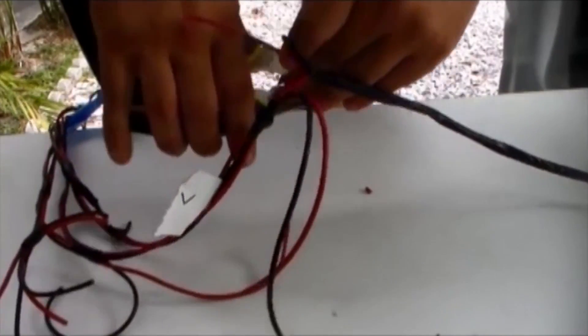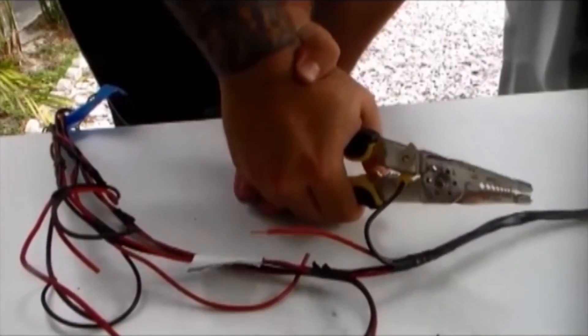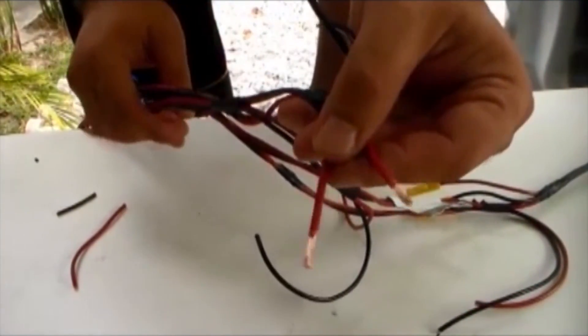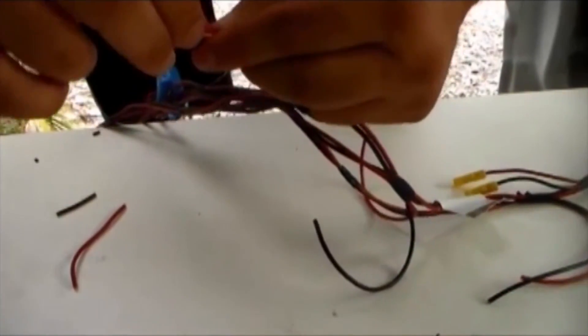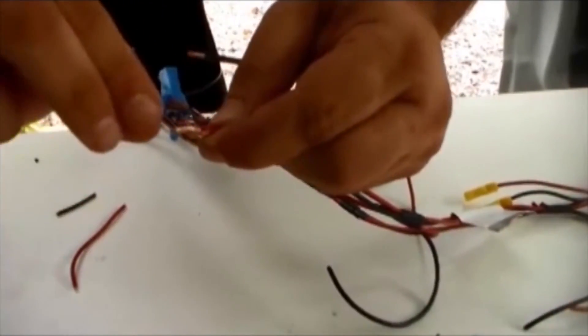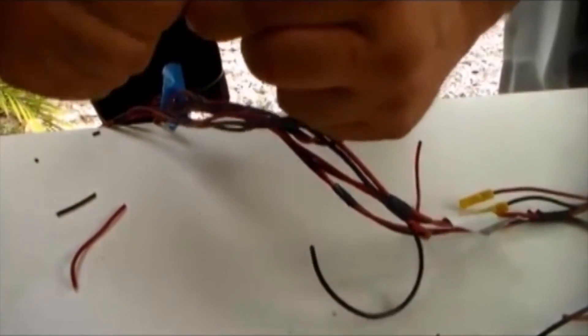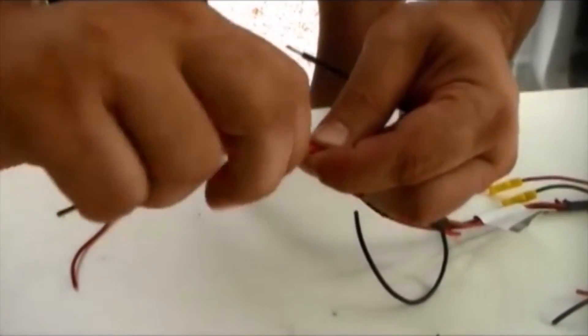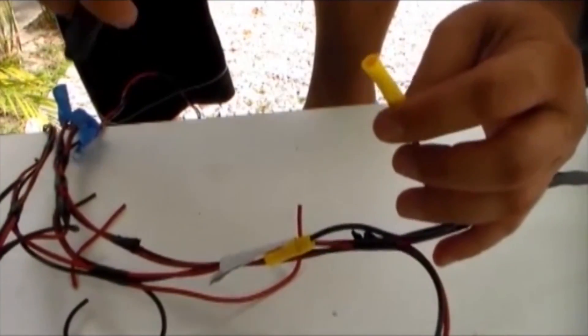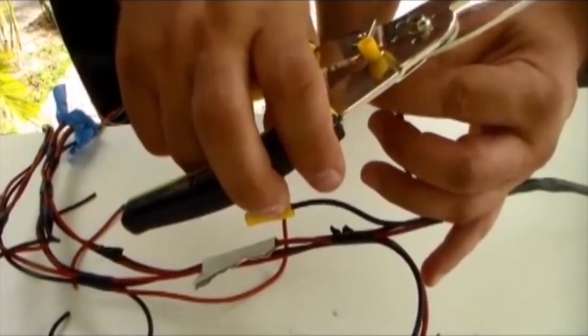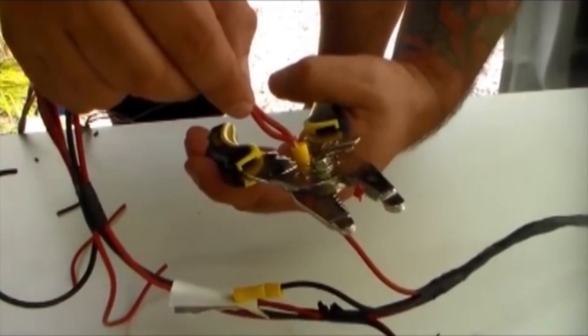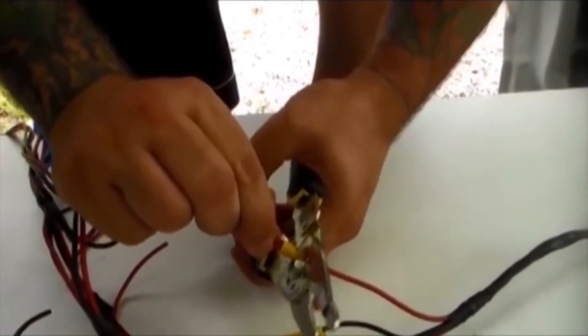Crimp it, make sure it's on there tight. You don't want it coming loose. There's the two wires. I got them stripped back further than I normally would because these two need to get twisted together. Do a very extreme twist with it like that, make sure they really wrap around each other so one doesn't slip loose. Then that will fit in that side. I'll get the crimp ready. Hold it and look down inside to make sure neither wires snag, that it slides in smoothly. All the way in there, then we crimp it.